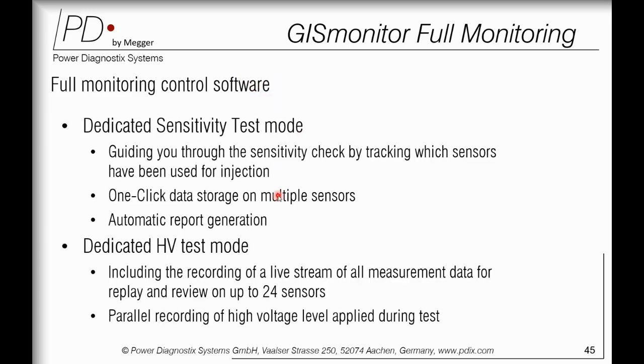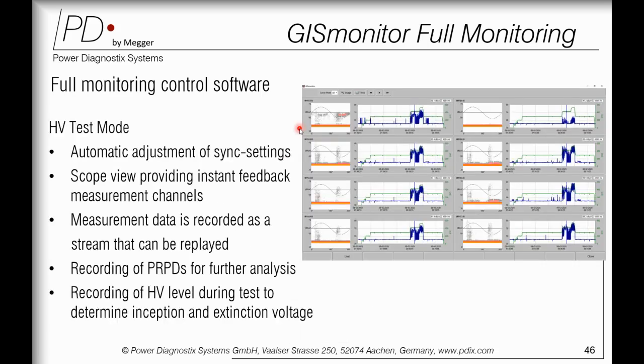And the GIS monitoring system, along with the software, also has a complete software for sensitivity verification tests as well as the HV test modes, which we have discussed previously. You can see the same pattern, it was the same snap of the software. It also has a dedicated adjustment, sync, and scope view. It records the data and you can replay it later, recording the PRPD for further analysis, and recording the HV level during the inception and extinction voltage measurements.